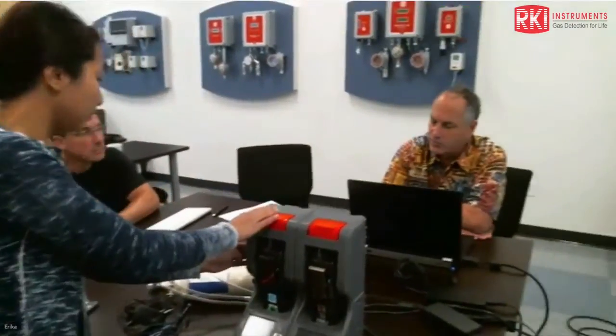So that's a difference with the other docks. The 6000 dock uses an SD card mostly because it has a lot more memory that way, so you can do downloading of data in addition to calibrations and bump tests when you're using it in standalone mode, and it'll save all the data to the SD card. So it'll still function. You can still do bump tests and calibrations without the card, but it won't save it anywhere except to the instrument.